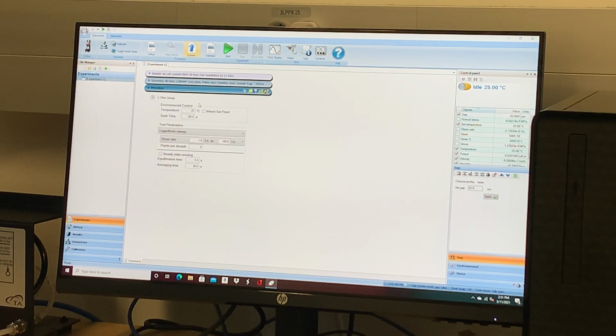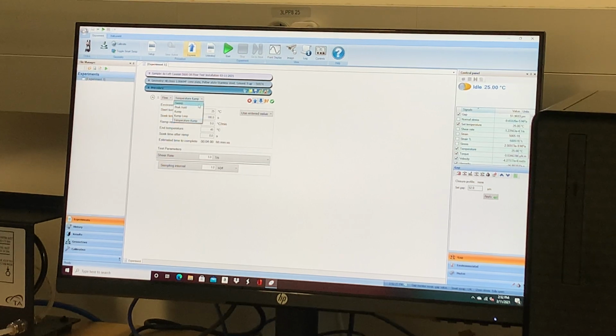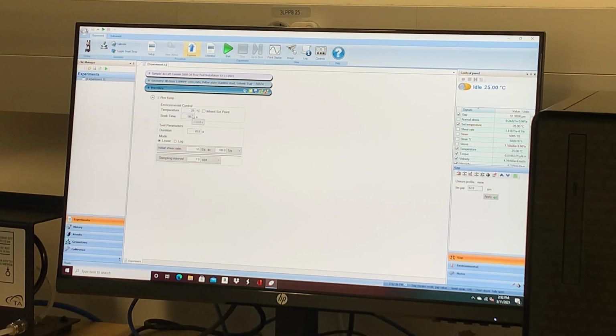Okay, but we're going to run a flow test. Under flow test, you've got some choices here. Peak hold is basically going to go to one shear rate and just sit there, right? Or ramp, it's going to ramp up from a low shear rate to a high shear rate. Ramp loop is going to go up from low to high and then back down. And then temperature ramp, which you would typically do with a plate. We're just going to do a ramp at 25C. It's been sitting there for a while, so we don't need a soak time. And we're going to run it for 240 seconds.